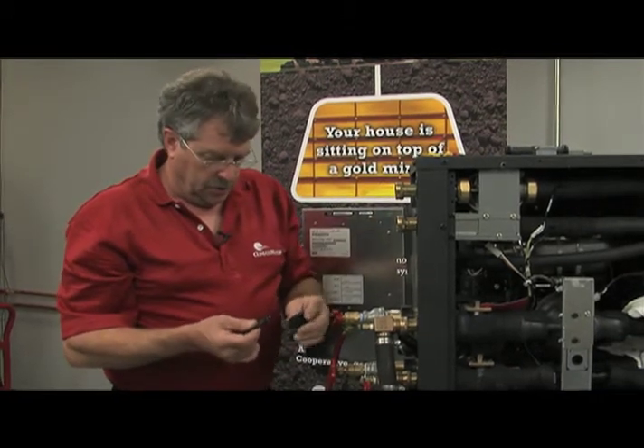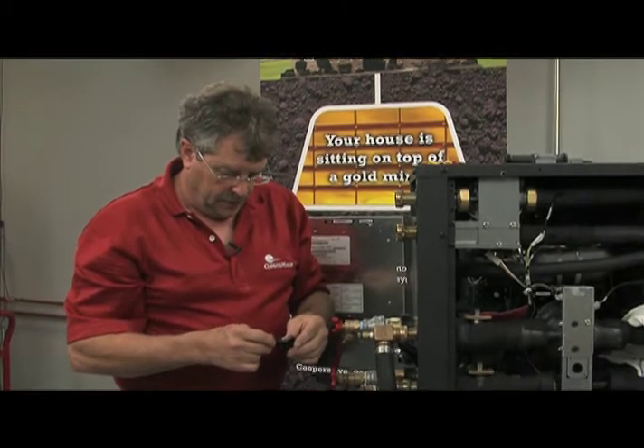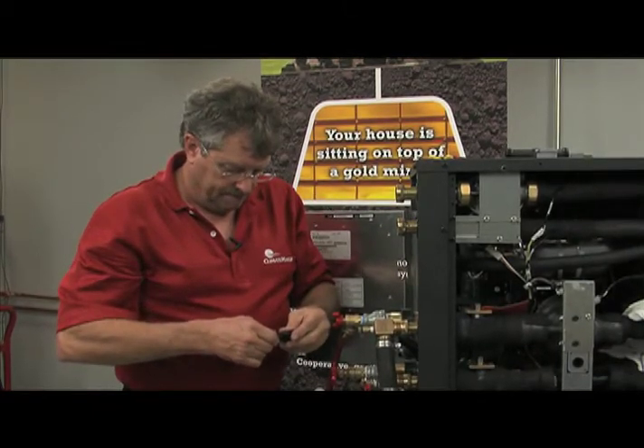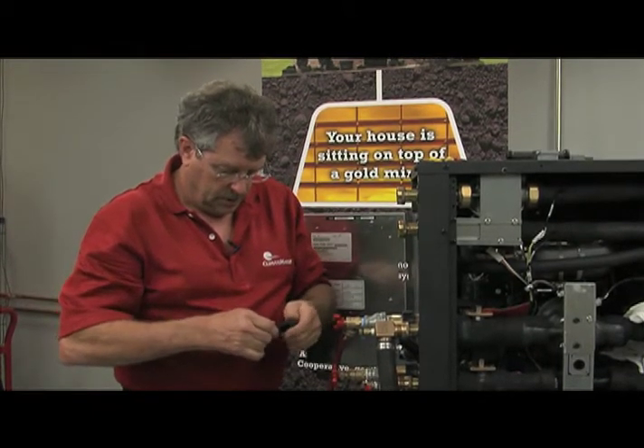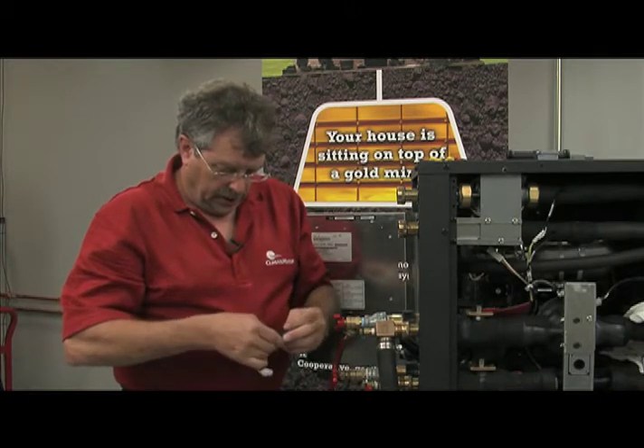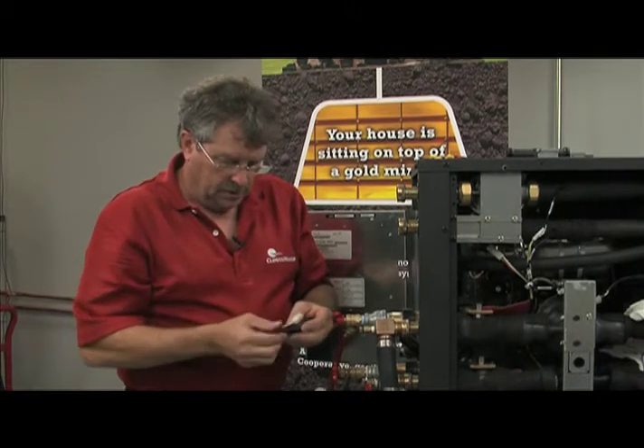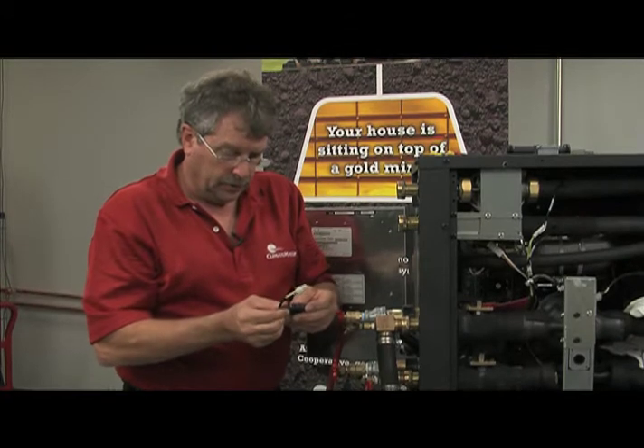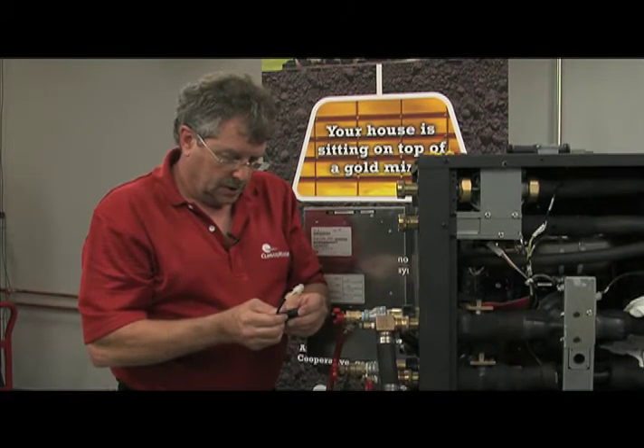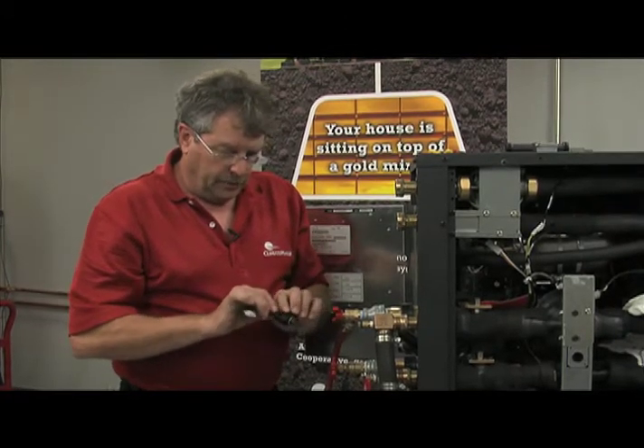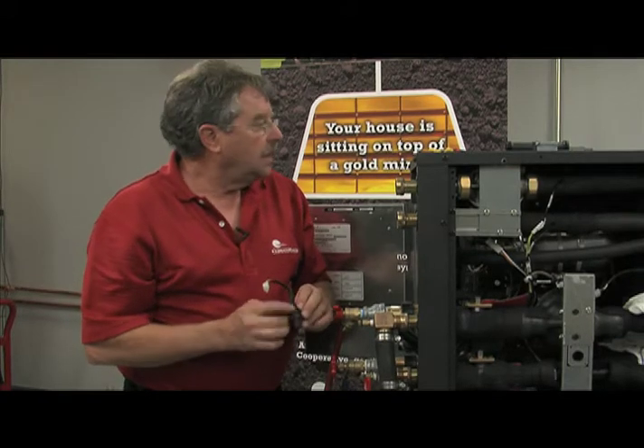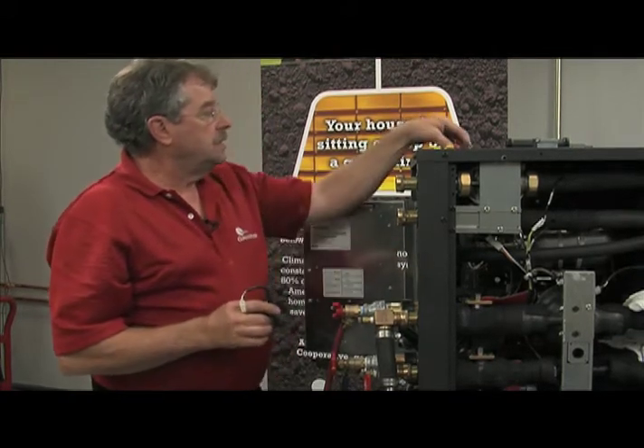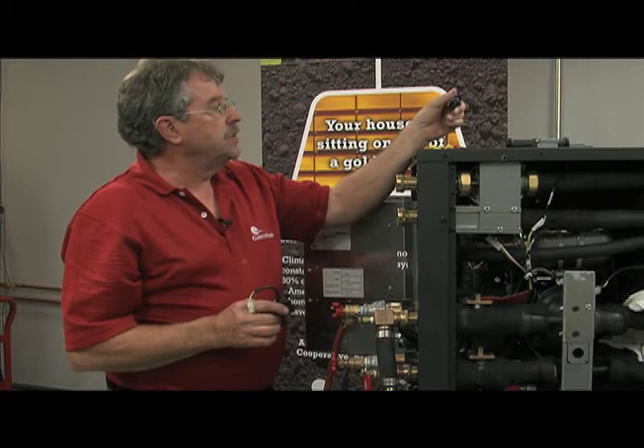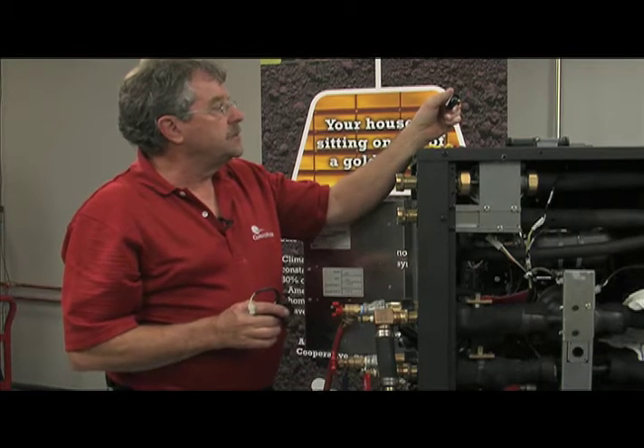Here's our new sensor. Again, we're going to verify that it's got a good connection here, and that the clips have reseated. I'm going to do another little gentle pull test. Now again, we've got a couple of O-rings here. You want to make sure you have two O-rings that you removed. You can see one of them's damaged, the other one's not there.